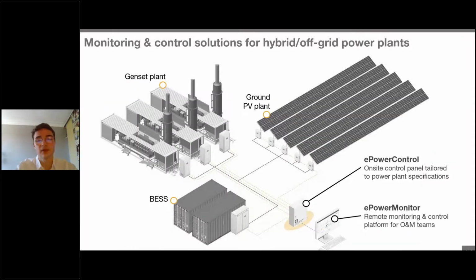Here you have an example of a microgrid that is totally off-grid with different gensets, being the grid-forming units, with the PV plant connected. Basically we have the HFS controller that will be managing this PV diesel plant, but we can also propose products from the e-power control portfolio.